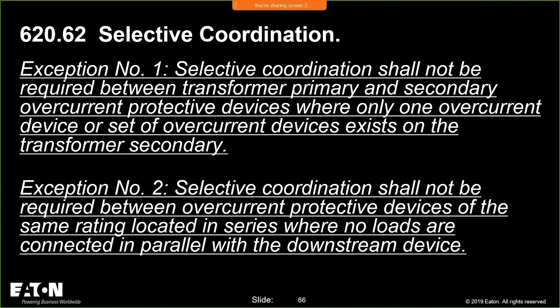Selective coordination shall be provided. Now these two exceptions came in because we pulled those in from the panel 13 guys who have Articles 700, 701, and 708. They pulled in those requirements to align with all of those areas where we have selective coordination requirements. My recipe for determining what devices need to selectively coordinate is this: you simply have to figure out, if a downstream device opens, what load does it take out? If the device directly upstream opens, what load does it take out? If they both take the same load out, then you don't have to selectively coordinate them. If taking out the upstream device takes out more loads than the downstream device, then you do have to selectively coordinate. An example of not requiring selective coordination is on the primary side of a transformer. That overcurrent device does not have to selectively coordinate with the device directly on the secondary of that transformer.